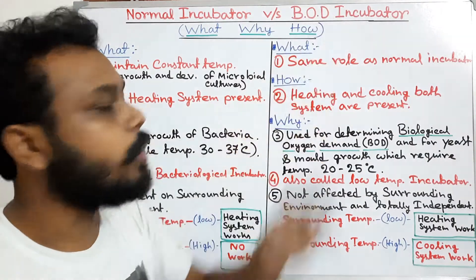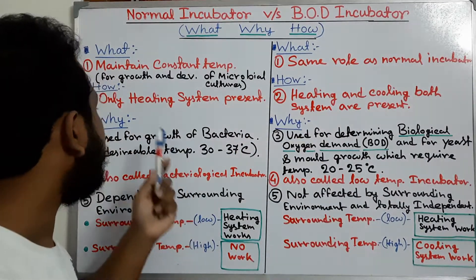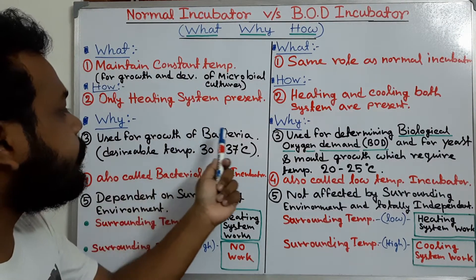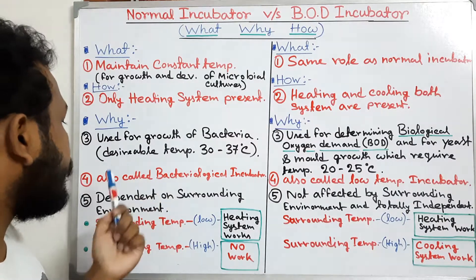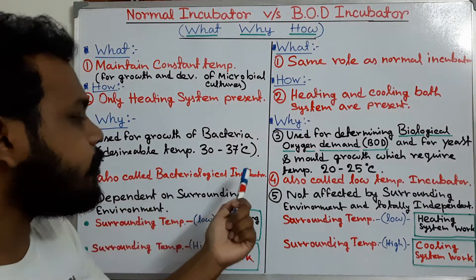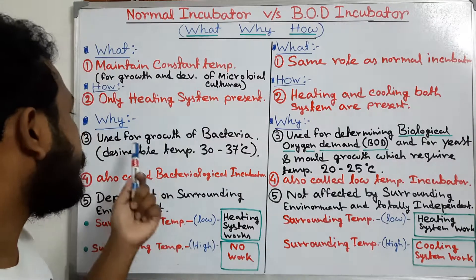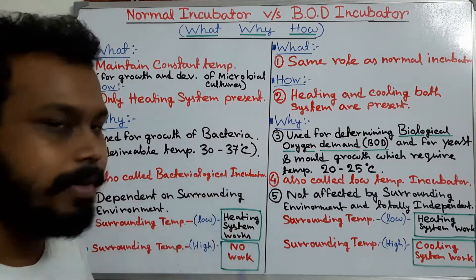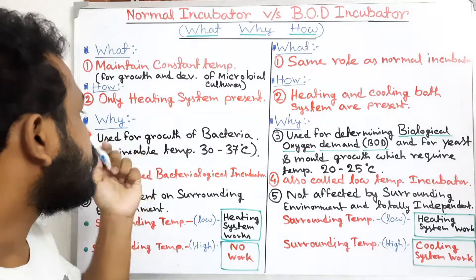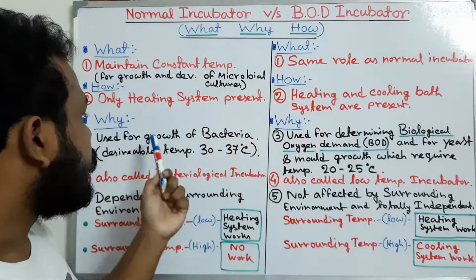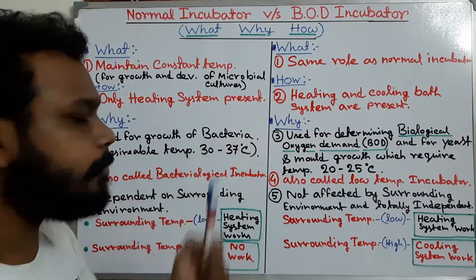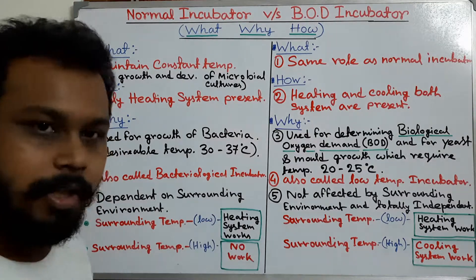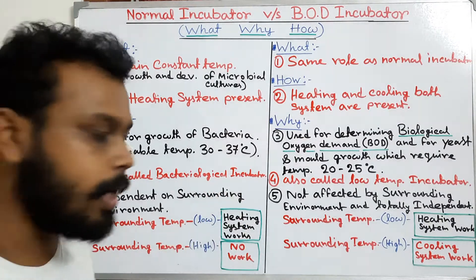The normal incubator is used for the growth of bacteria, and that's why it is also called the bacteriological incubator. The desirable temperature for this is 30–37°C.